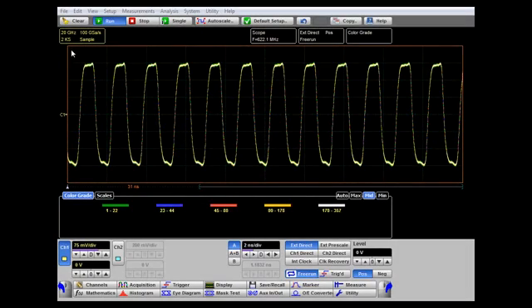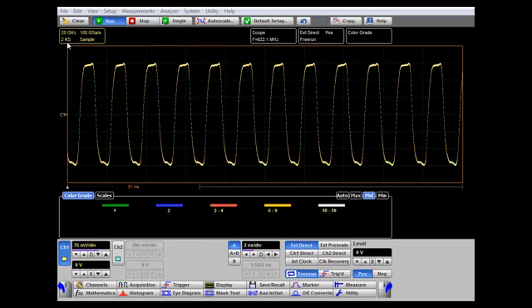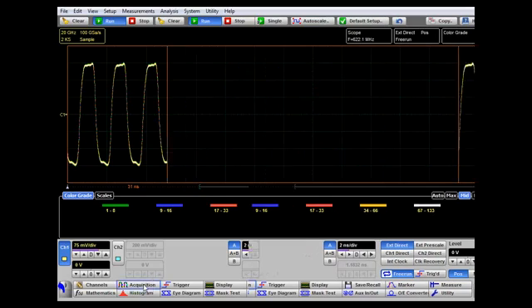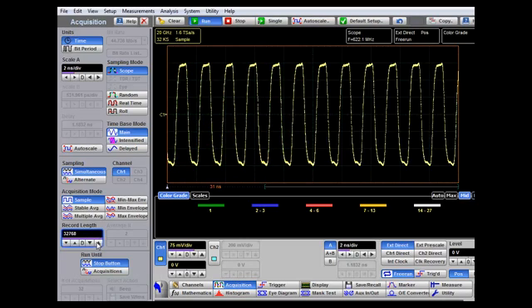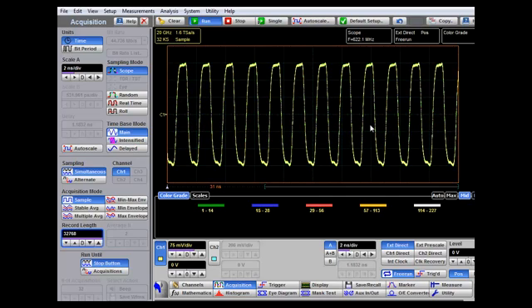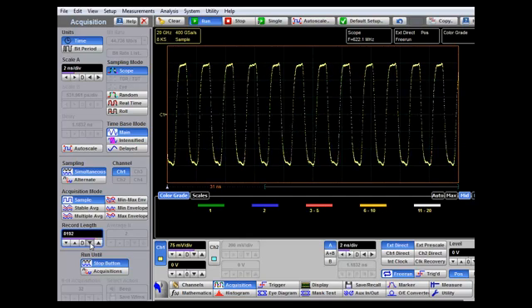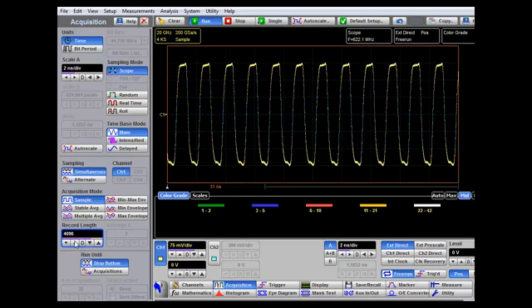It's possible to increase the record length beyond 2000 samples if more time accuracy is required. This is available in the acquisition menu. The default value is 2048, but it can be increased as high as 32,000 points in this instrument. There is a trade-off: the longer the record length, the longer it takes to acquire the data. In this case I select a 4096 record length.